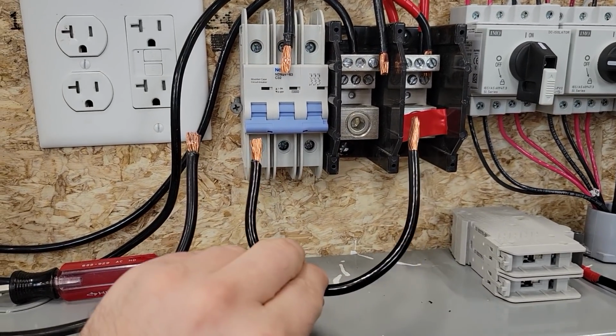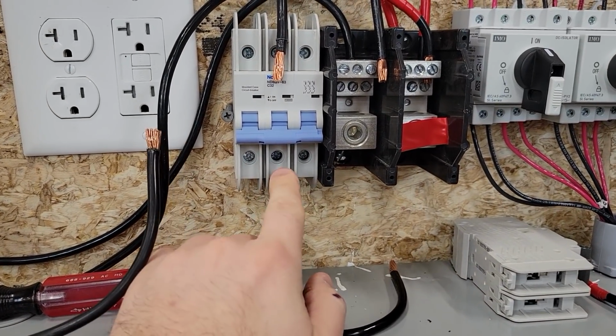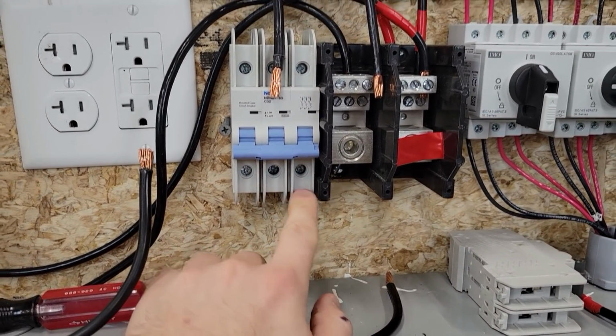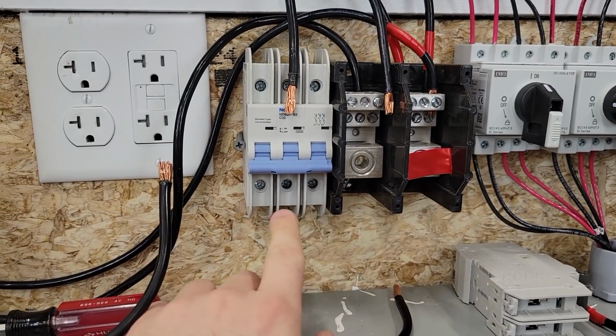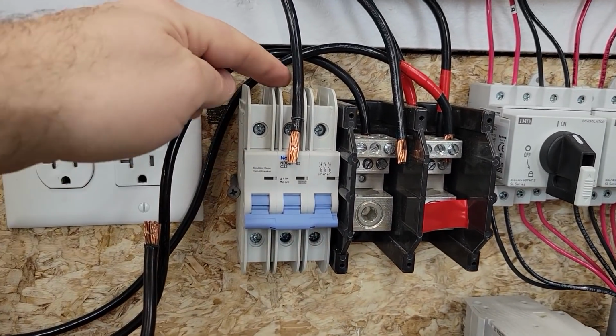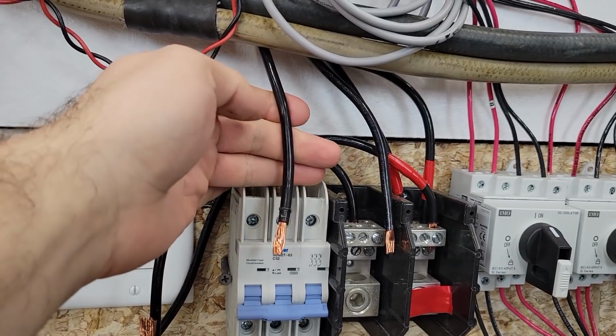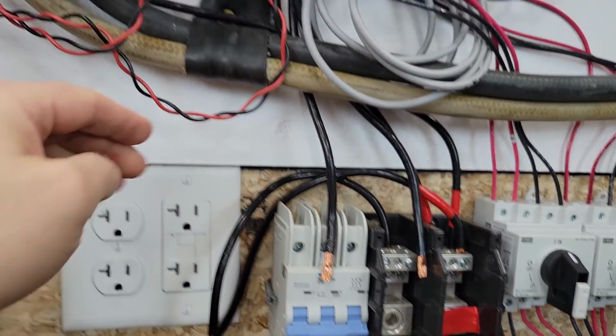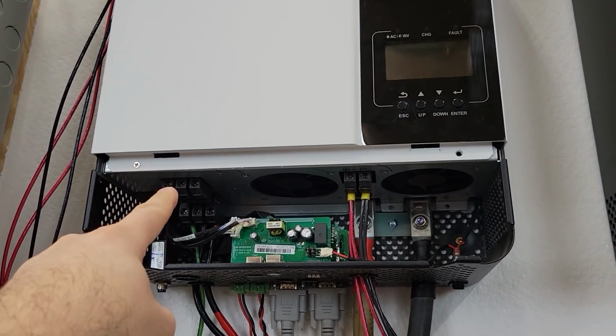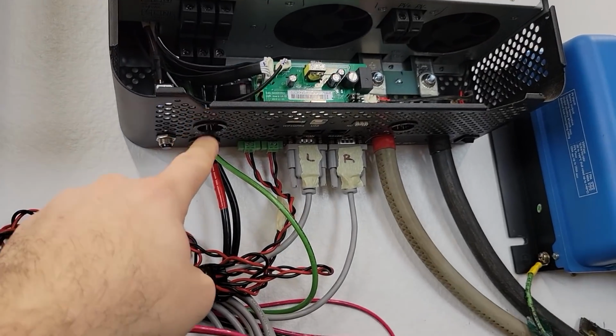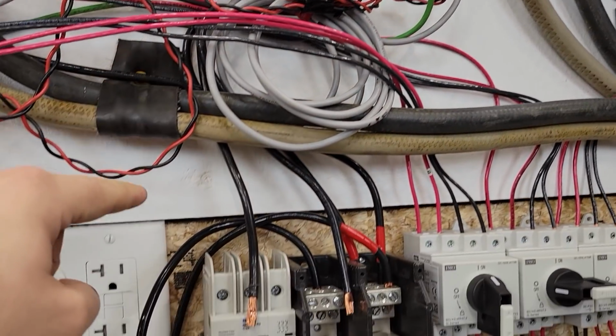So I'm going to take these jumpers. We're going to bring both, these are L1 and L1. We're going to put them to the terminal block on the output side of the breaker. But coming in the top of the breaker is going to be L1 from this inverter and L1 from this inverter. So we're going to run them through.